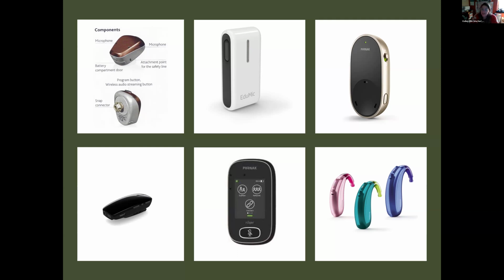Another big one that I see mostly with the Roger touchscreen mic is loss of connection. You can look on there to see if a device is connected. Once that microphone gets a certain distance from the hearing aid and the receiver, it no longer shows that it's connected, but I promise it is. 90% of the time it's still connected. It just doesn't show on the screen.